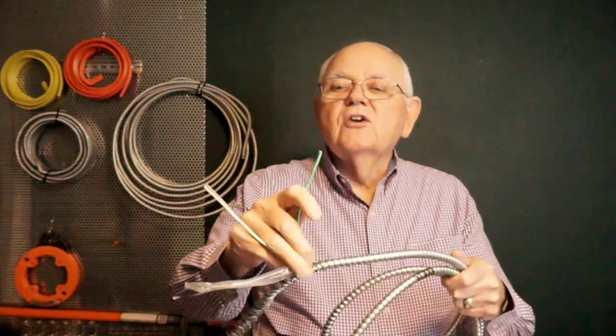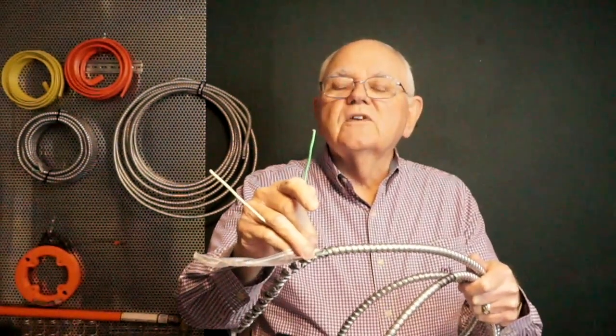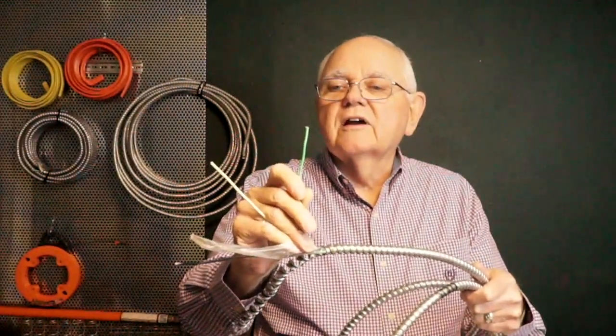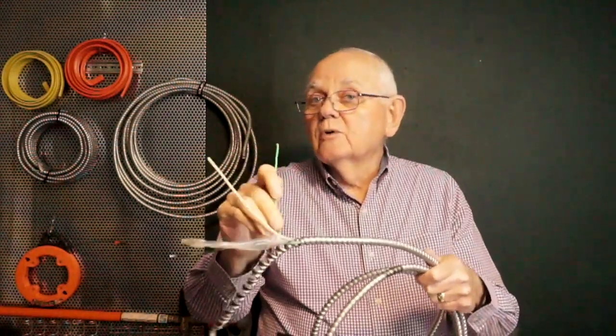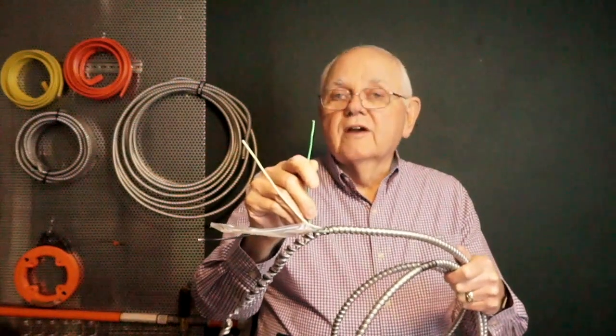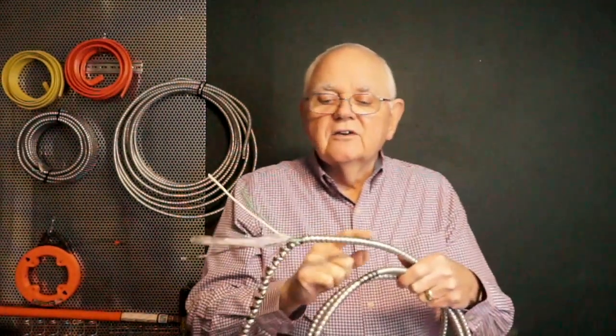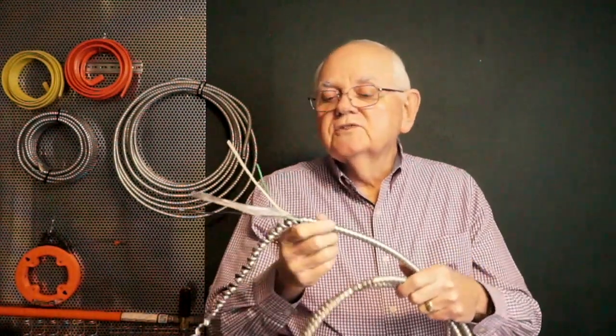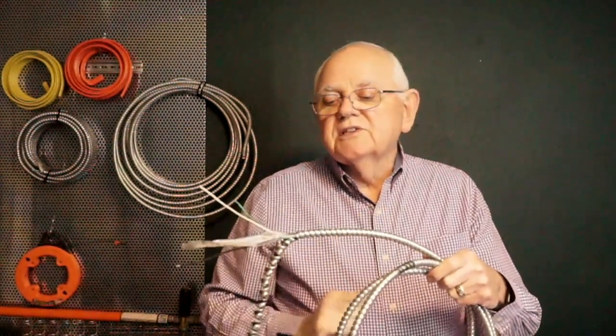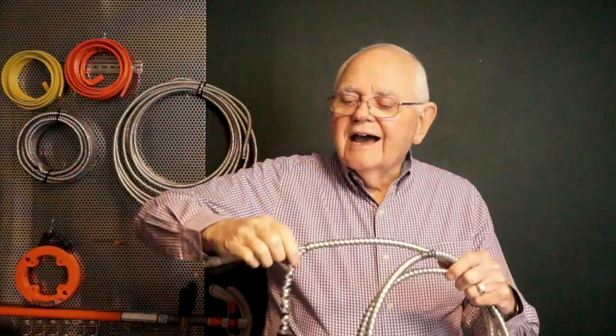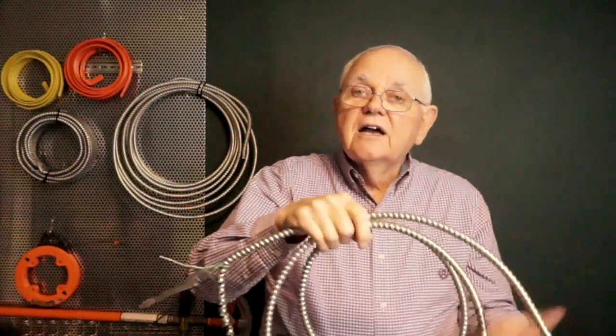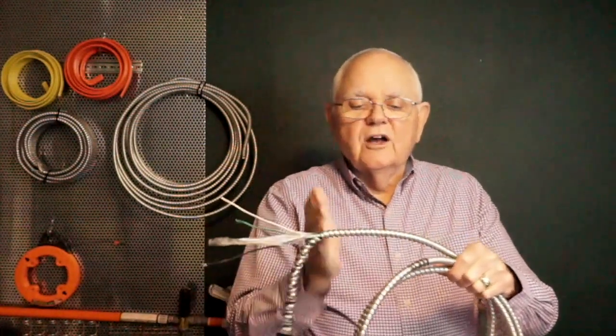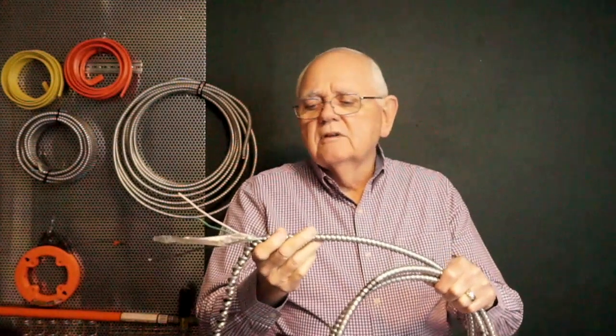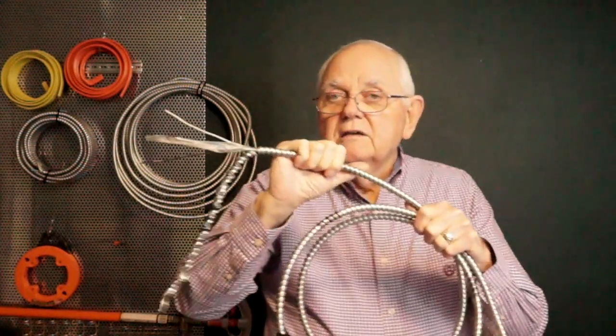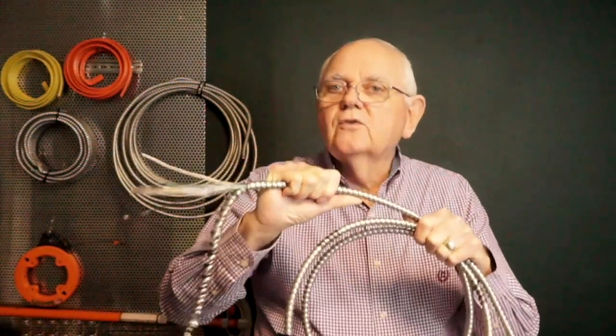So certainly I can have a green insulated copper wire inside of this MC cable. That obviously can be used as my equipment grounding conductor. Also, I could have a bare copper or aluminum wire in there. That may be used as my equipment grounding conductor. Or I could take an interlocking tape type like this, or one of the other 2 types, either the corrugated continuous or the smooth continuous. And when they manufacture it, on the outside of the Mylar sheath, they could run, say, a bare aluminum conductor the entire length of the MC cable. And it would be in contact with all of these convolutions throughout the entire MC cable. Then we could use the sheath of the metal-clad cable as the equipment grounding conductor.